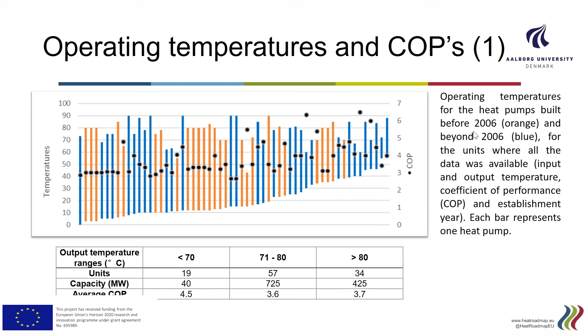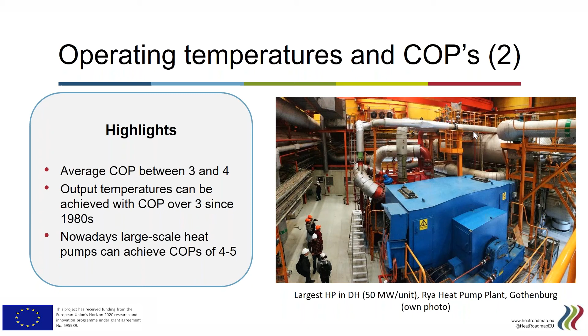As I mentioned, heat pumps can provide COPs between 3 and 4, and that is also the case for the heat pump in the picture, the one in Gothenburg, which can achieve these COPs even though it was built in the 1980s. If technology built back then can provide this kind of COP, nowadays new technology can easily provide COPs of 4 to 5, as I will show you in the next slides.